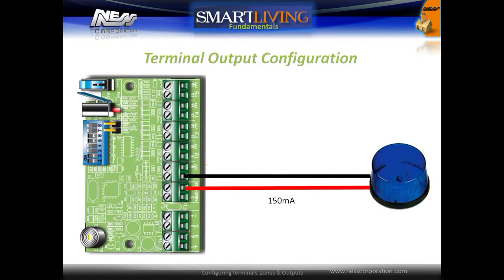A terminal has sufficient power to drive screamers and strobes directly. As this diagram shows, the positive of the strobe connects to an auxiliary +12 volts and the negative connects to the terminal. Only a single strobe or screamer can be driven off of a terminal directly.